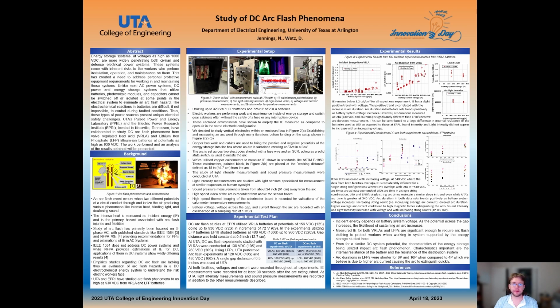This incident energy becomes interesting for LFP batteries at 500 volts. When comparing this to VRLA batteries, we see that even at 500 volts, we do not encroach upon the 1.2 cal per centimeter squared or arc flash boundary. In the case with LFPs, we do, however. Looking at the data from EPRI, we see that their incident energy is much lower at 500 volts, 600, 700, 800, and encroaches closely at 1.2 cals per centimeter squared, around 1,000 volts.